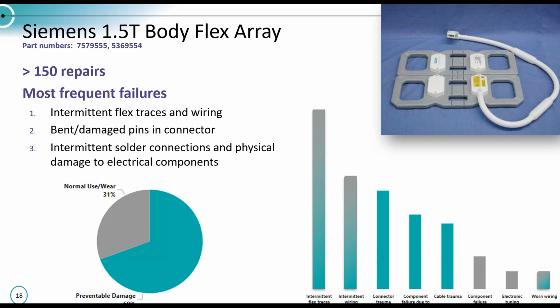The third failure ties in with the top failure—the intermittent solder connections are a result of the intermittent flex traces and wiring for this model. So there's a lot of green on this slide, meaning preventable damage, which comes inherently with flex coils. This is what we see coming into our facility: almost 70% are a result of preventable damage.